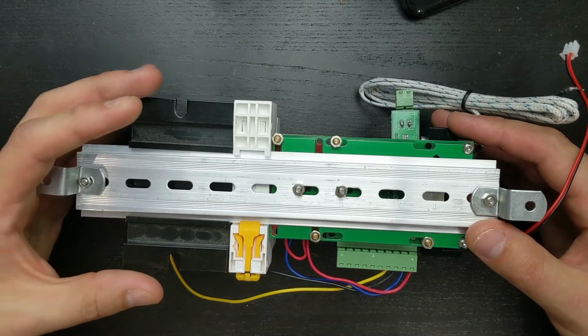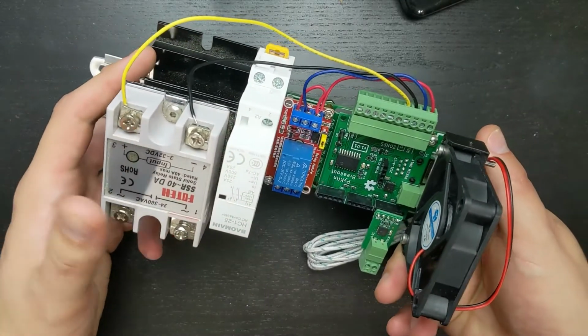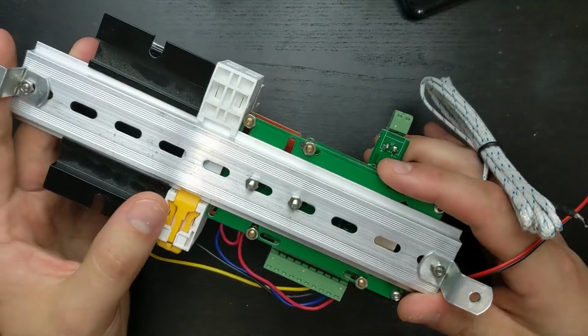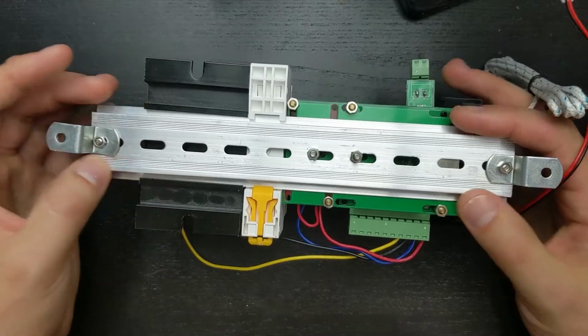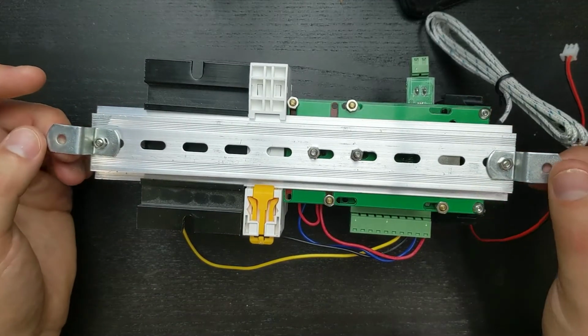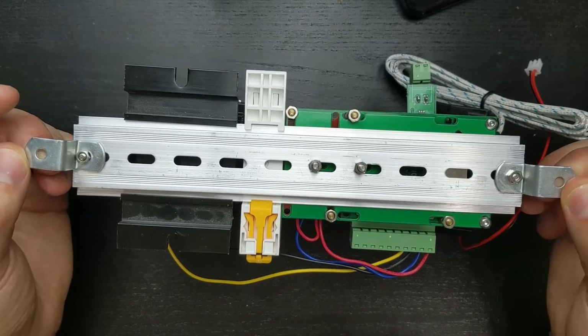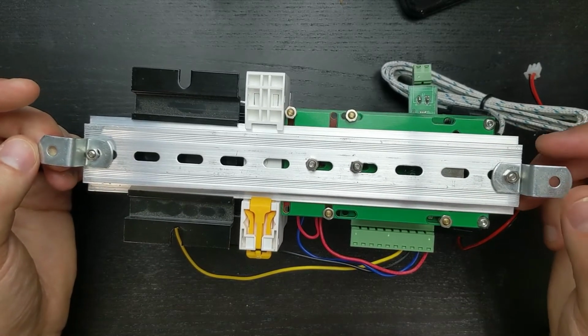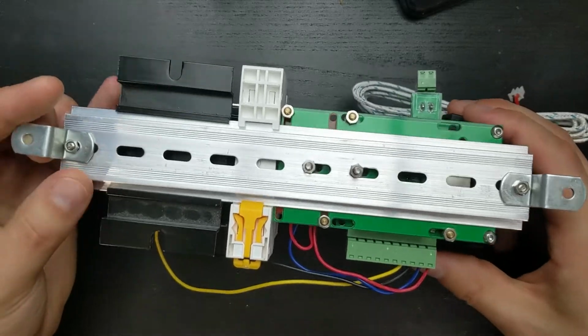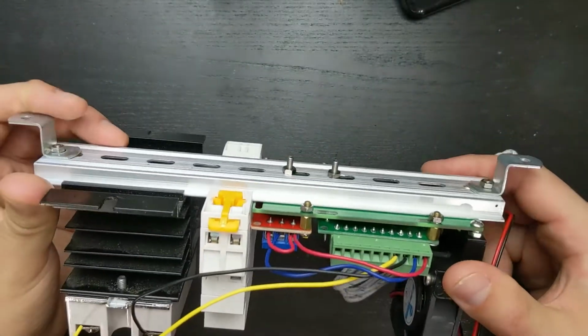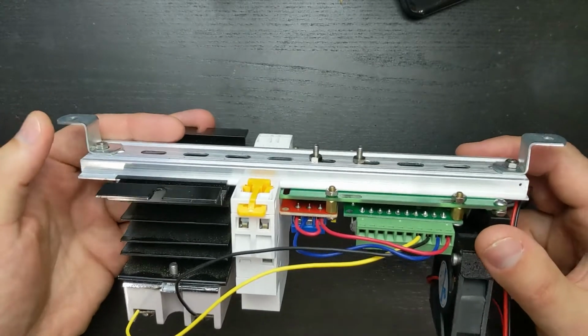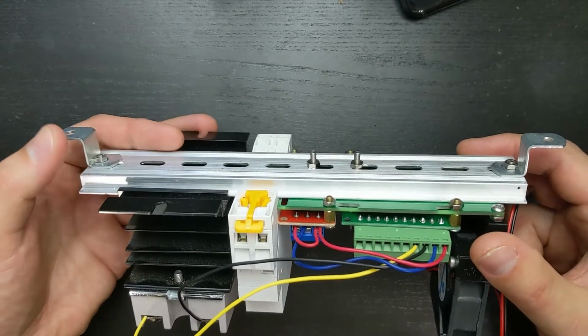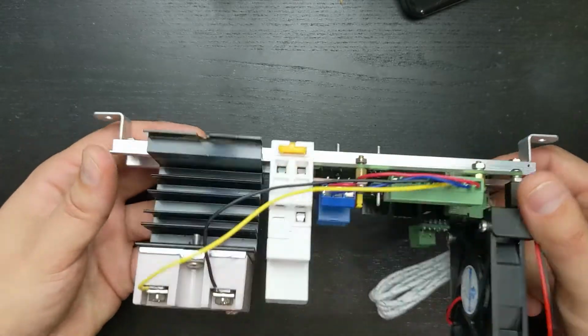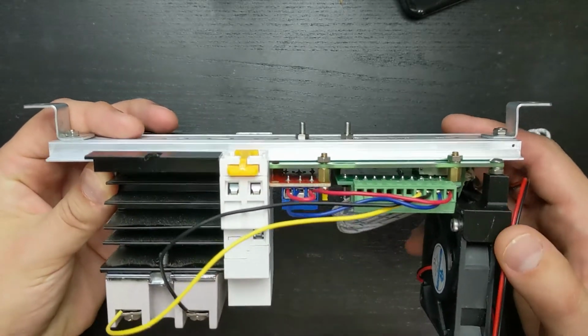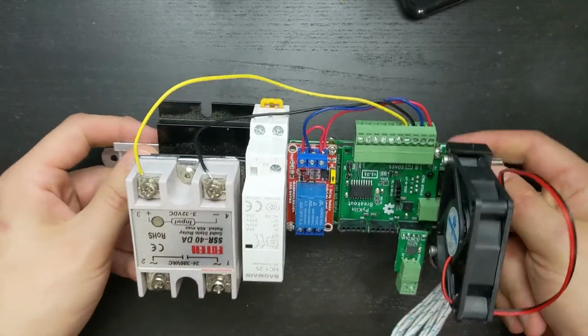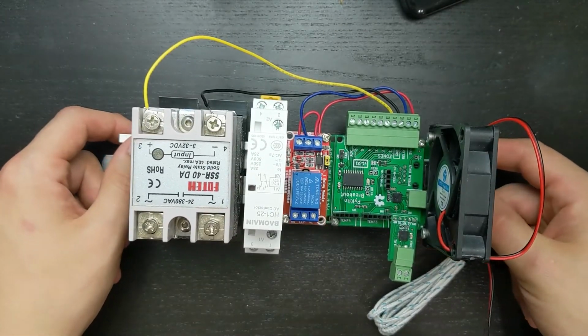To mount your electronics. The nice thing is the solid state relay and the contactor both mount to it right out of the box. So I have this DIN rail that everything's connected to, and I have these offset clips. And so these offset clips are actually from picture frames. So you can buy them for framing and that sort of thing, but they're actually really great for what we're trying to do here, which is to create a heat break between the outside of your kiln and the electronics that are mounted on the outside of it. So let's flip this over and let's just kind of walk through things.